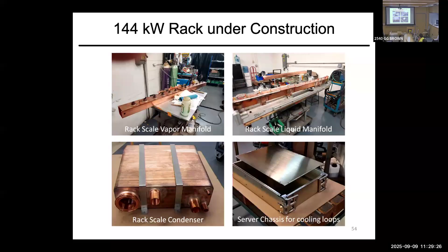These are the manifolds for essentially vapor and liquid. And this condenser - believe it or not, water has such an incredible heat transfer coefficient that this in-rack condenser can take care of everything. We even envision that at a 300 kilowatt rack, we could have 2 condensers, and going even higher to half a megawatt, we could do 3 condenser systems. So it's a very scalable system, completely water-based.